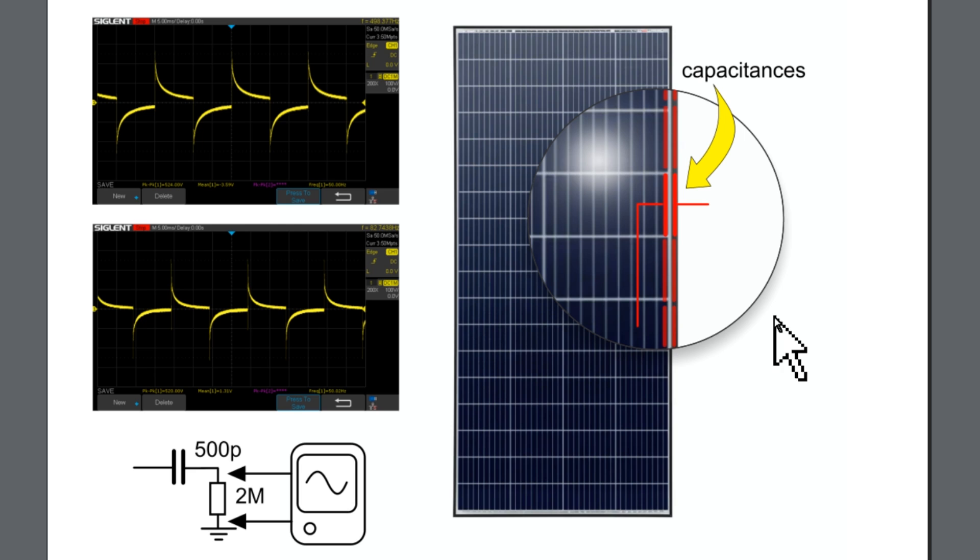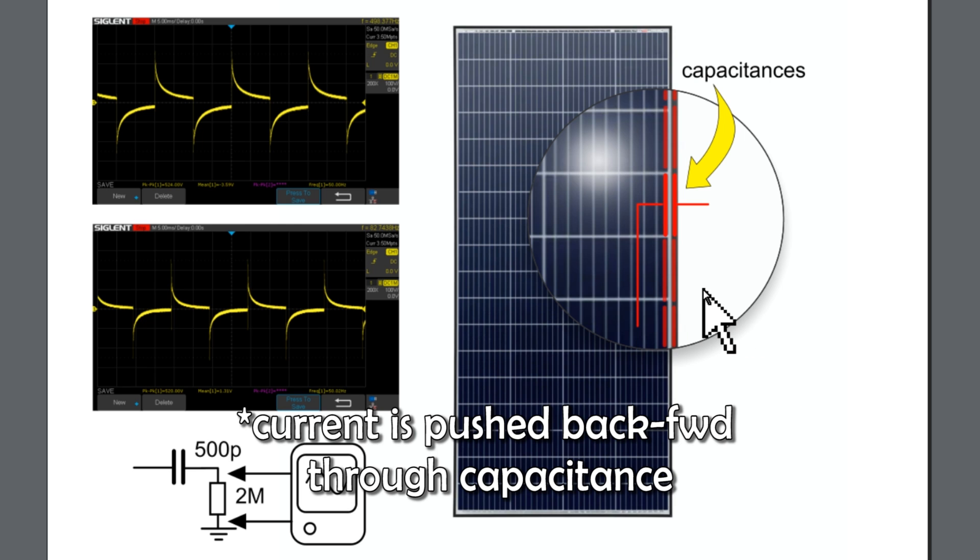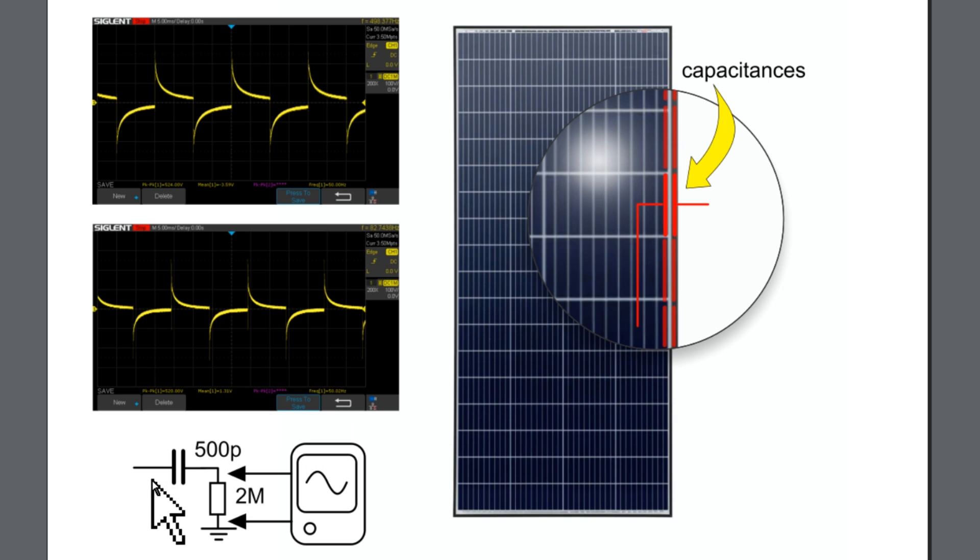And if this point is connected to ground, here we have a current that will flow through this capacitor. It can be seen in this way, here we have this capacitor that is the capacitance that we have here across the edge of the cells and the frame of the panels.